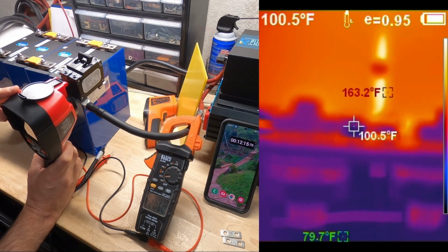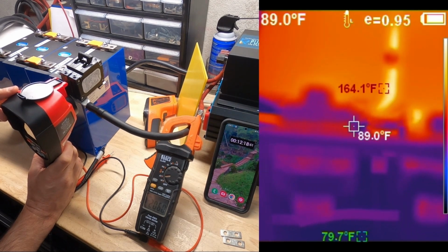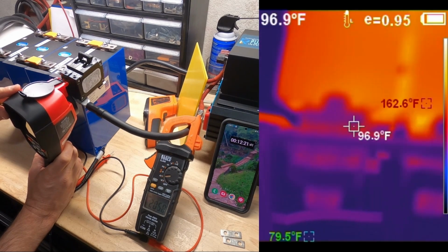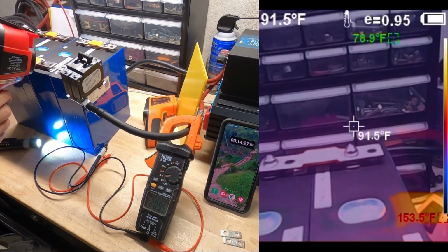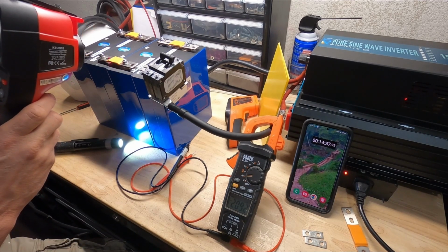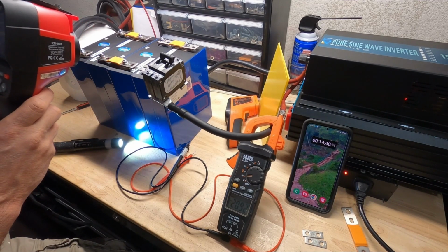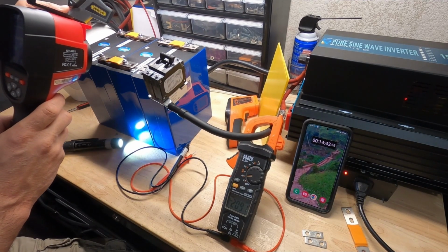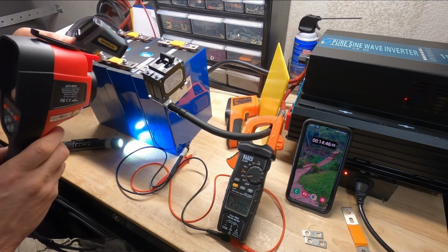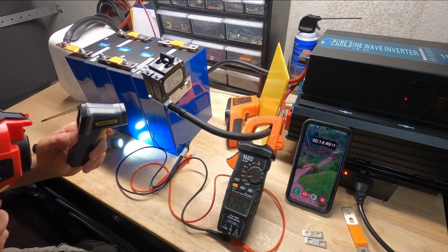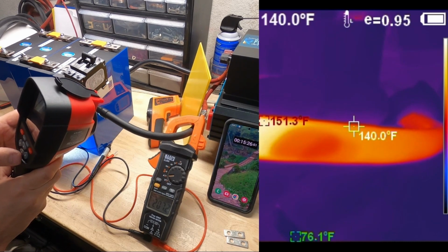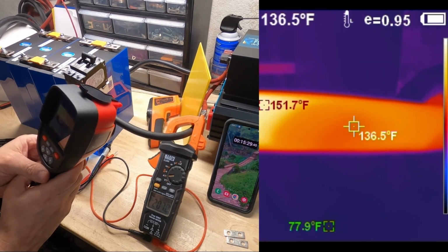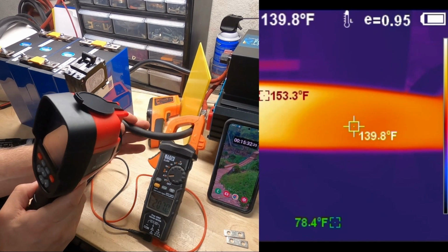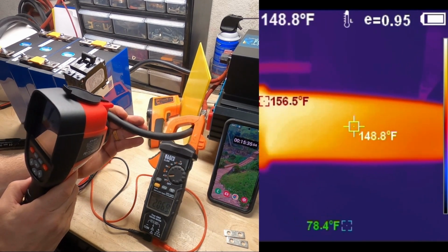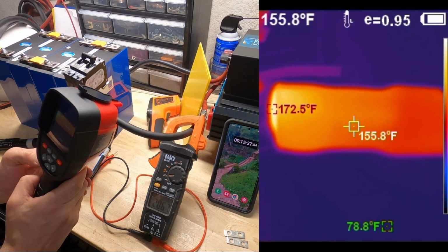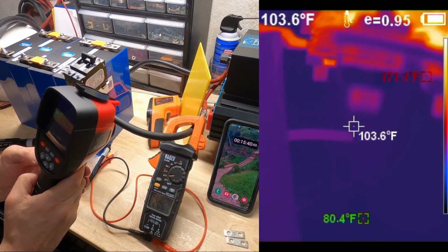So we're seeing similar temps on the breaker internally as the previous test, 160, 170 degrees. Let me cross check it with another one. 90 degrees on the bus bar, 92. 90 degrees, 93, 92. Now the battery cable is getting up there at 150. But now we're running on 16 minutes, so.